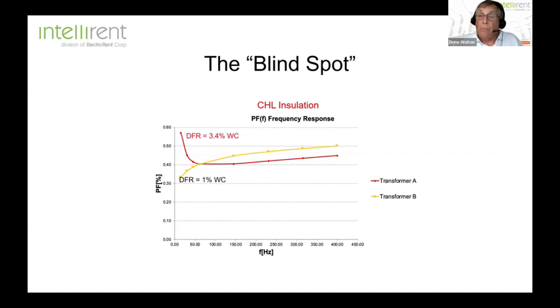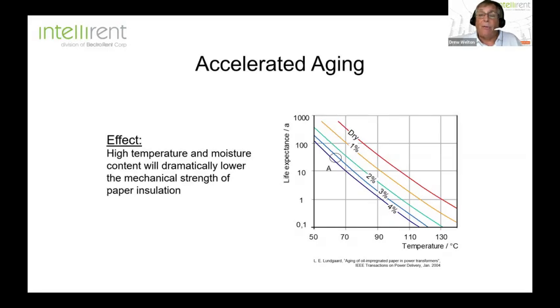Now, you'll see here we measured this transformer at 60 hertz and it all looked identical. But when we change our frequency indication, you'll see one transformer A much higher, transformer B much lower. But again, you'll notice at 60 hertz, you don't see much difference here. Okay, when we do a test called dielectric frequency response, one transformer is coming in at 1%, the other is 3.4. Now, what that indicates in terms of the age of the transformer is quite significant. Okay, the age expectancy of transformer B with the drier insulation, you've got 100 plus years at less than 70 degrees C operating temperature. The other transformer, not so good. Maybe 10, 15 years in terms of its life expectancy. Now, if you start to increase that temperature, those numbers get even worse.